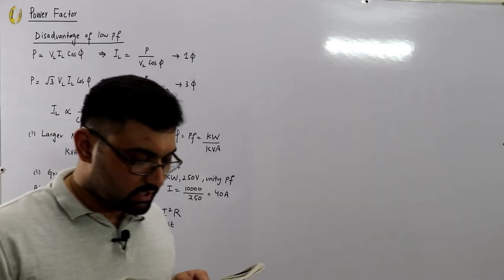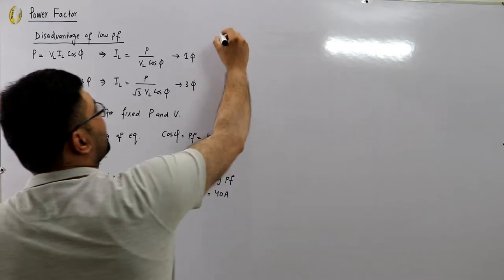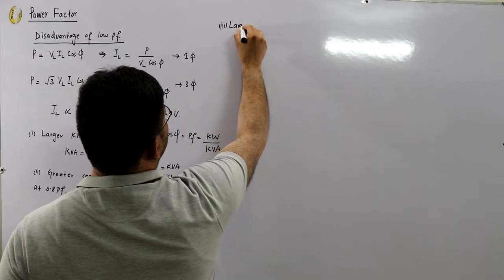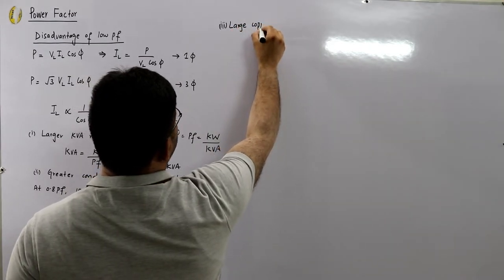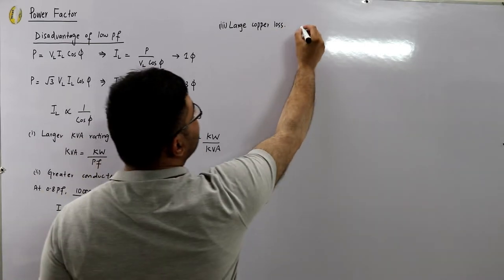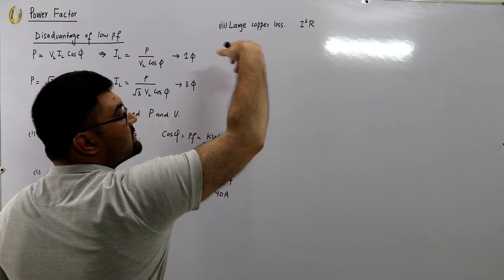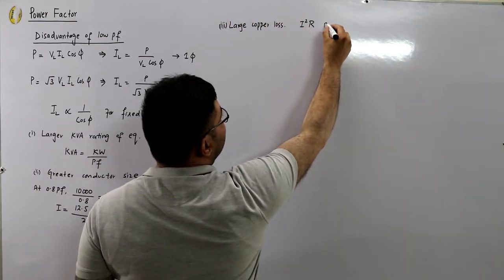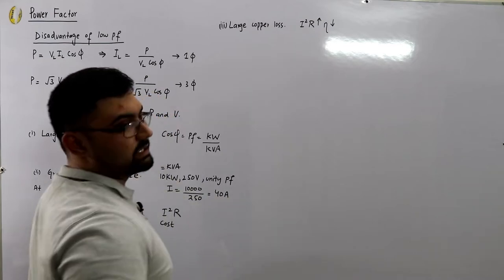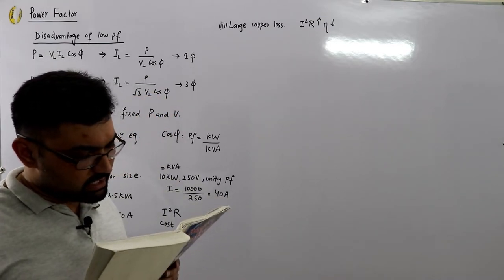The third disadvantage is large copper loss. Due to the higher current drawn at low power factor, the I²R power loss increases, which results in poor efficiency of the system.